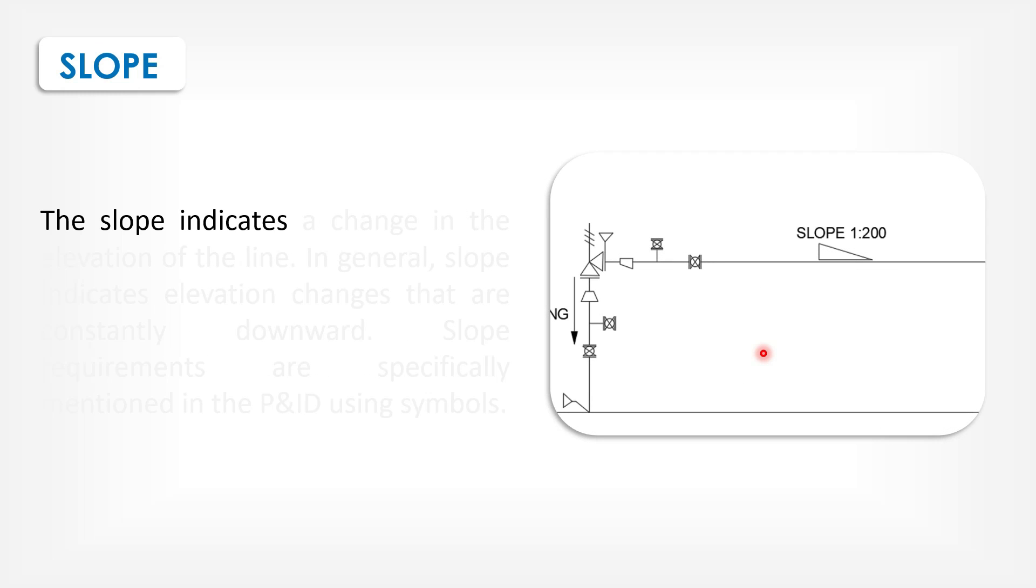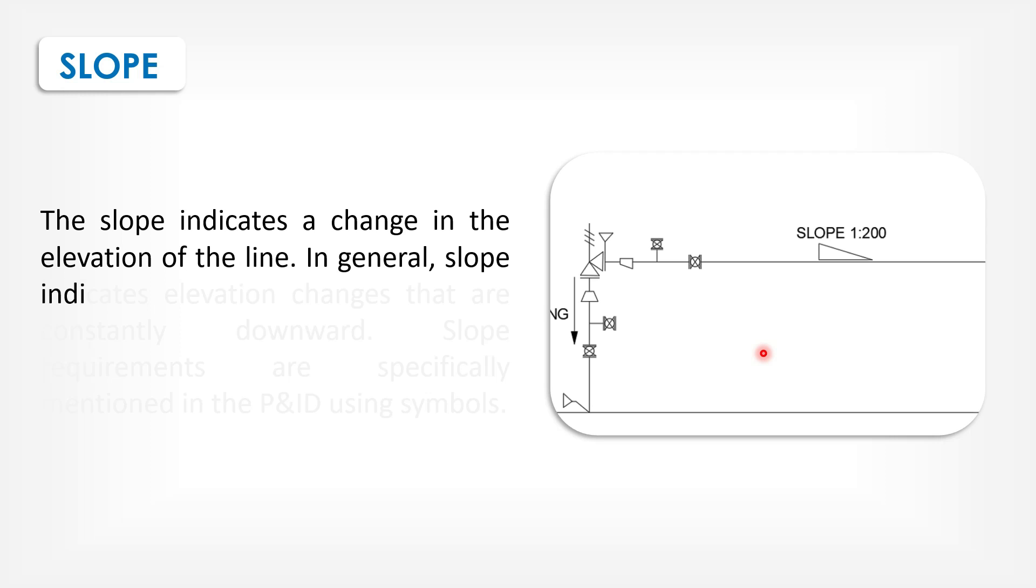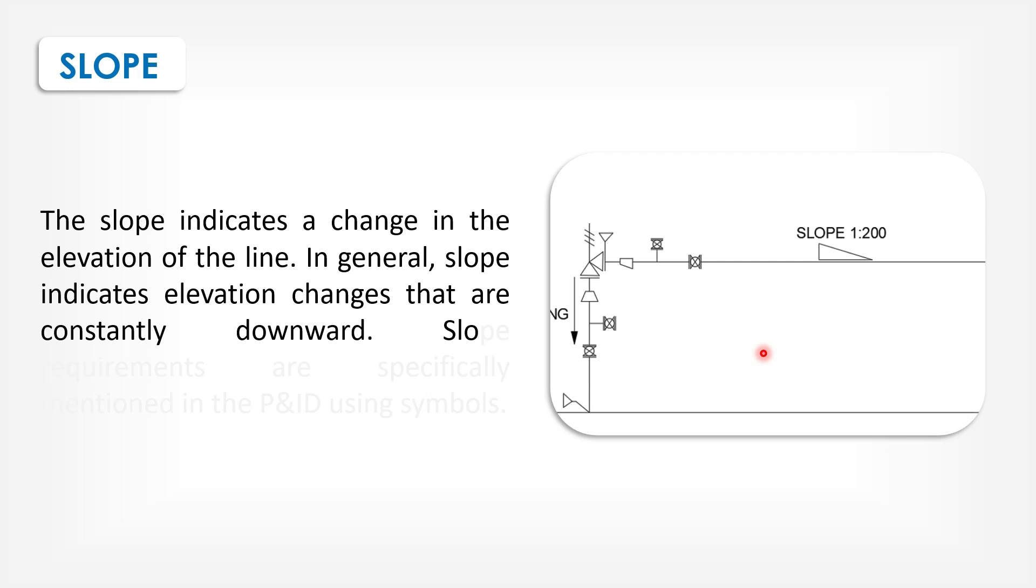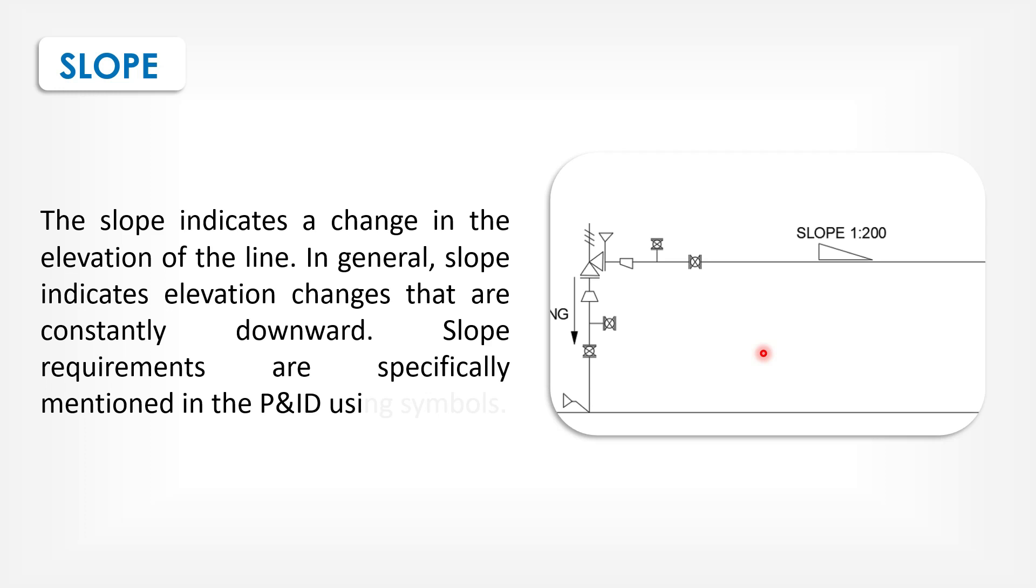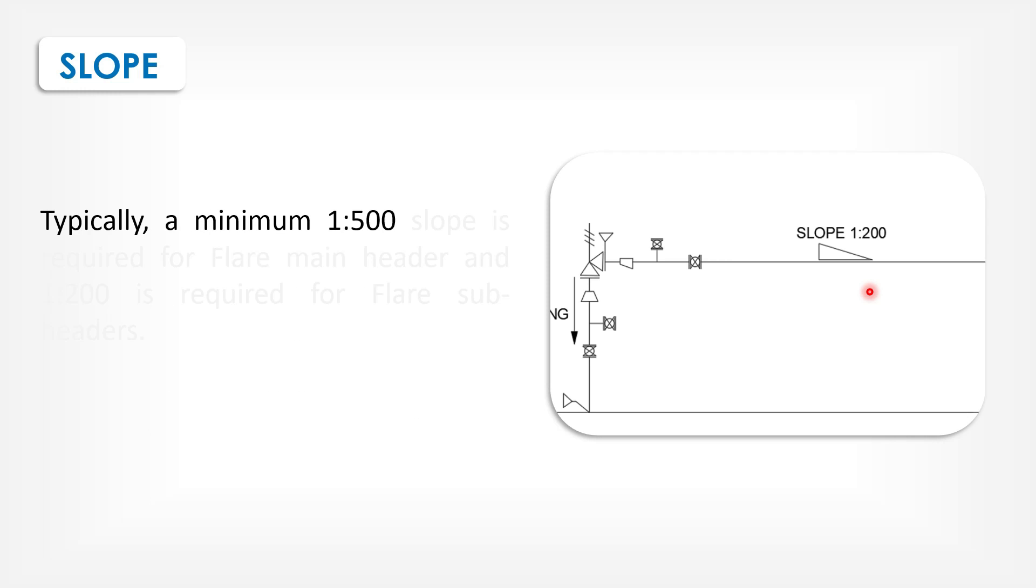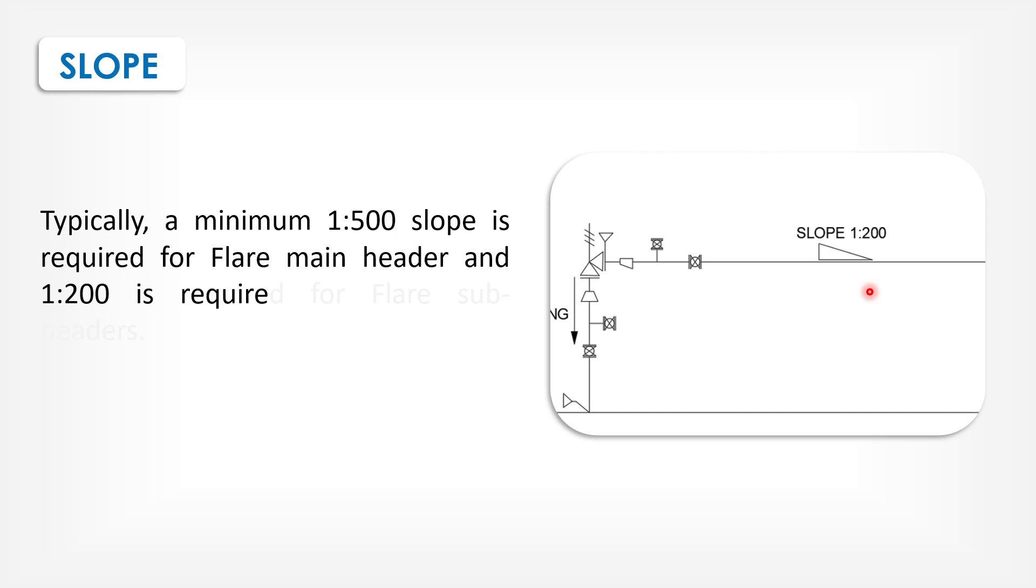Slope. The slope indicates a change in the elevation of the line. In general, slope indicates elevation changes that are constantly downward. Slope requirements are specifically mentioned in the P&IDs using symbols. Typically, a minimum 1:500 slope is required for flare main header and 1:200 is required for flare sub-header.